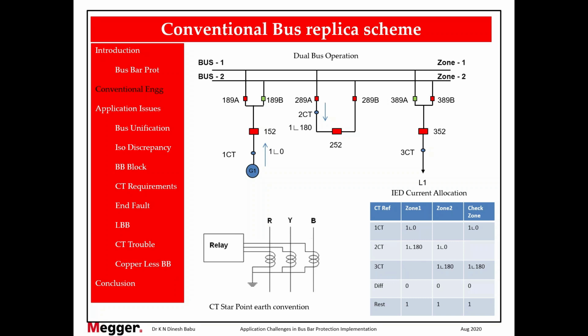Now, what would be the current direction of 2CT in zone 2? So this you have to see. CT is earthed towards bus 1, but current is flowing away from bus 1. Therefore it is 180 in bus 1. But in zone 2, what is happening? CT2 is earthed away from zone 2 and current is flowing towards zone 2. If it is out of phase, it has to be 180.